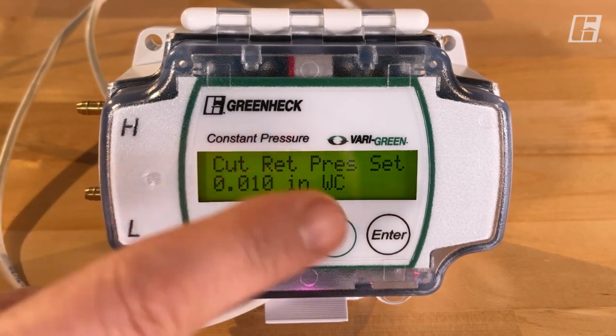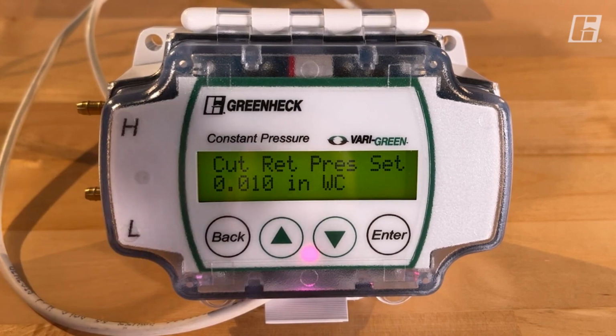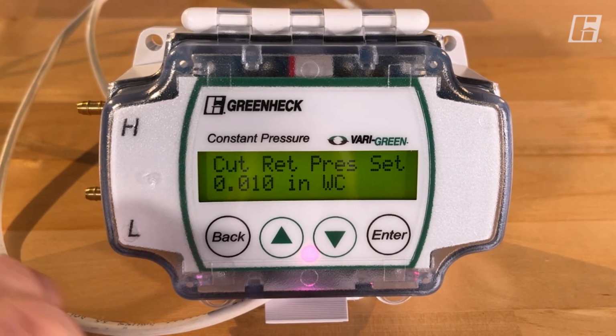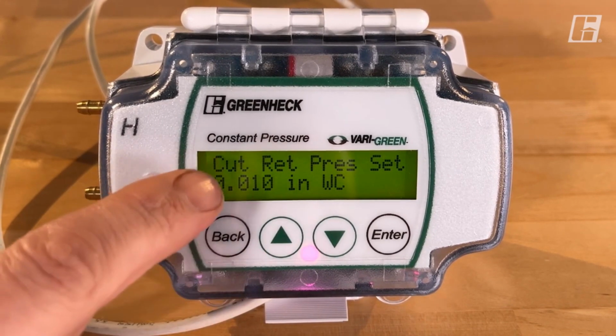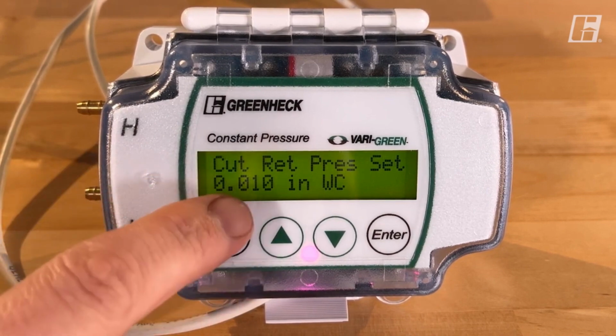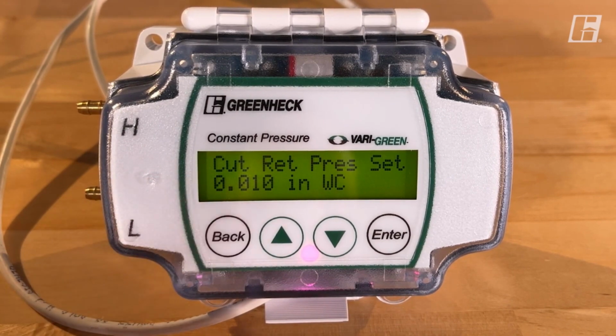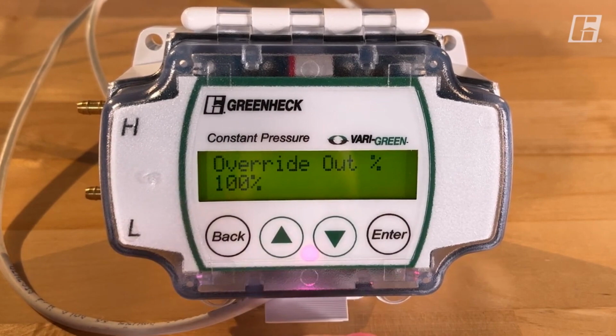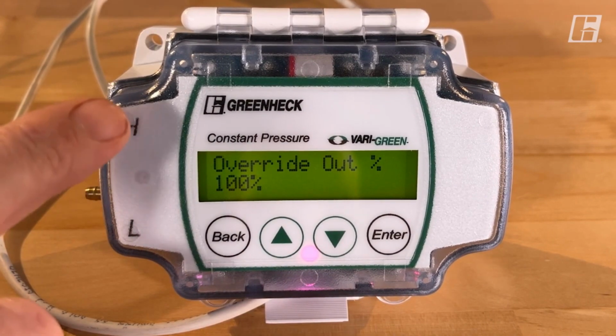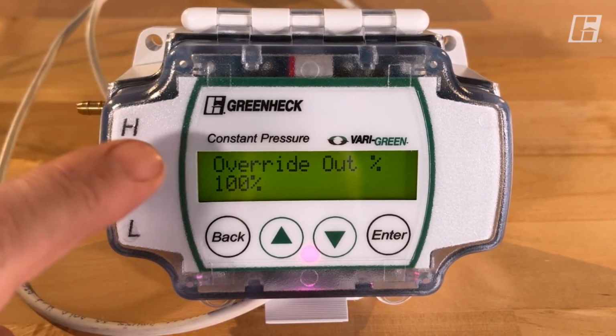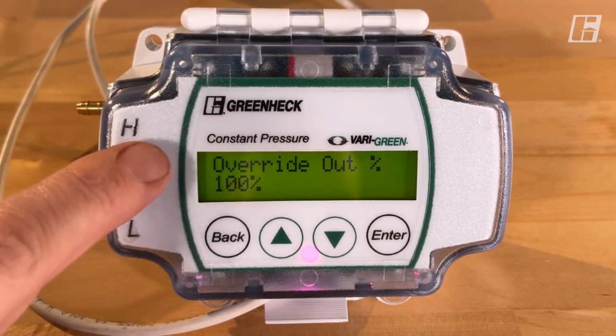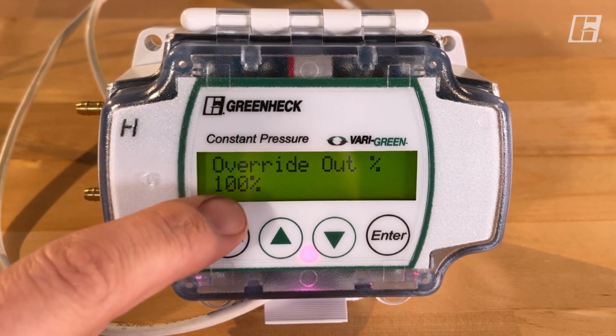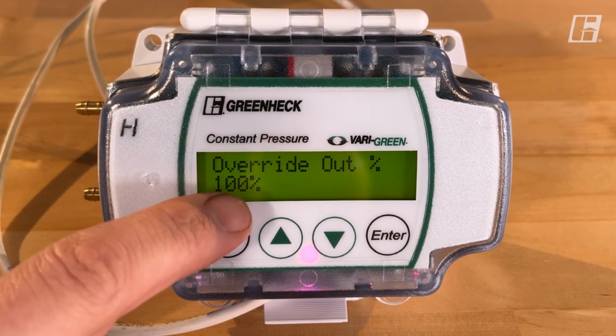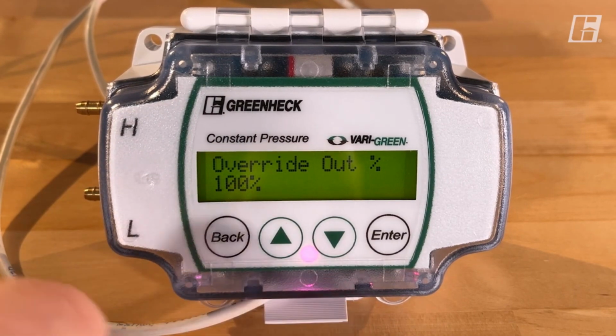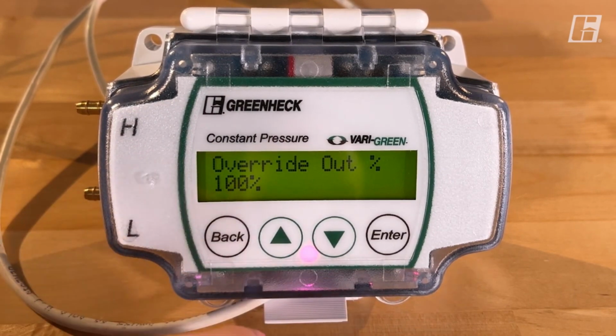Cutout return pressure set point. This is asking how much of a pressure change there needs to be for the fan to start up again. And here we have 1/100 of an inch. Override. There is that override terminal on the inside. When that sees continuity, this is the speed the fan will be running at. And you can set 0 and anything between 20 and 100.